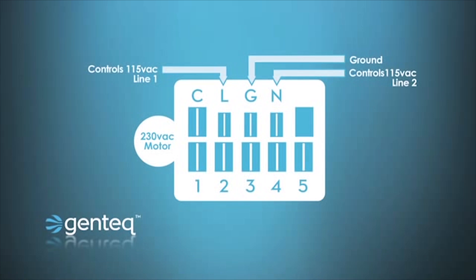In both cases, the voltage input to the motor can be plus or minus ten percent, and these motors will work on both 50 and 60 Hertz power. It is also important to note that these are not dual voltage motors. One is built at 115 volts and one is built at 230.